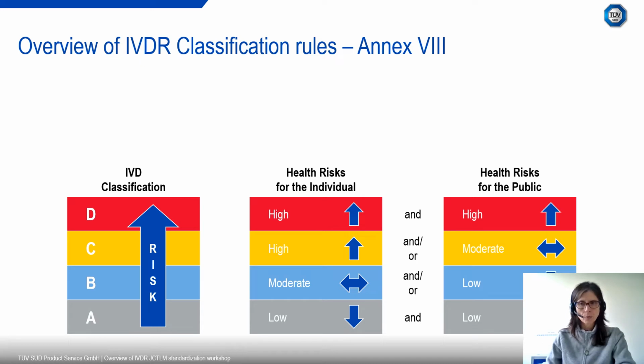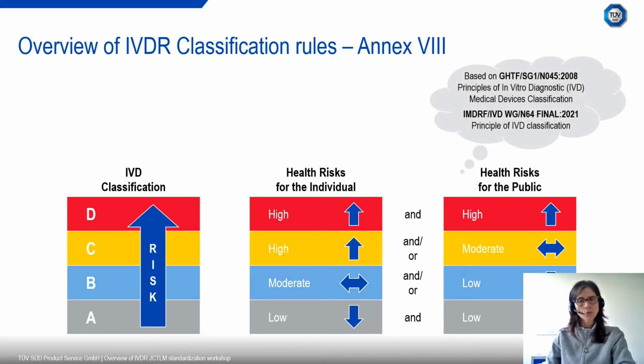This rule-based classification system is new for the European Union, but is not new per se, as it was described by the Global Harmonization Task Force back in 2008. And actually, the International Medical Device Regulators Forum revised this document earlier this year, but maintaining the philosophy of classification based on risk, taking into account several rules. These rules are described in Annex 8 of the regulation.